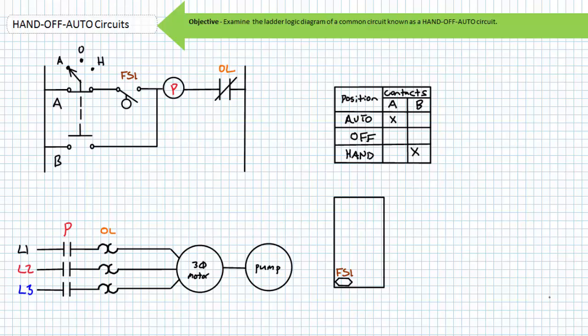Note this circuit does not use momentary manual switches or holding contact as would a three-wire control circuit. Once a quantity of liquid has been emptied from the sump, the float switch would reach its reset level and reopen, disabling the pump.